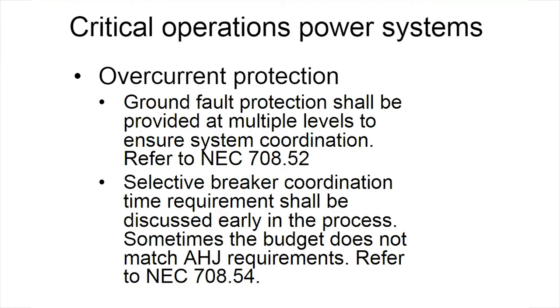Overcurrent protection, this is a good subject. Ground fault protection shall be provided on multiple levels to ensure system coordination. This is different from any other one. Yes, on COPs, you have to provide ground fault protection to ensure that one fault does not trip a main, that your feeder will trip first. I'm sorry, I used the word branch circuit, that is incorrect. It will be your main or your feeder. Branch circuit, you don't have to provide it. This is not the feeder level.